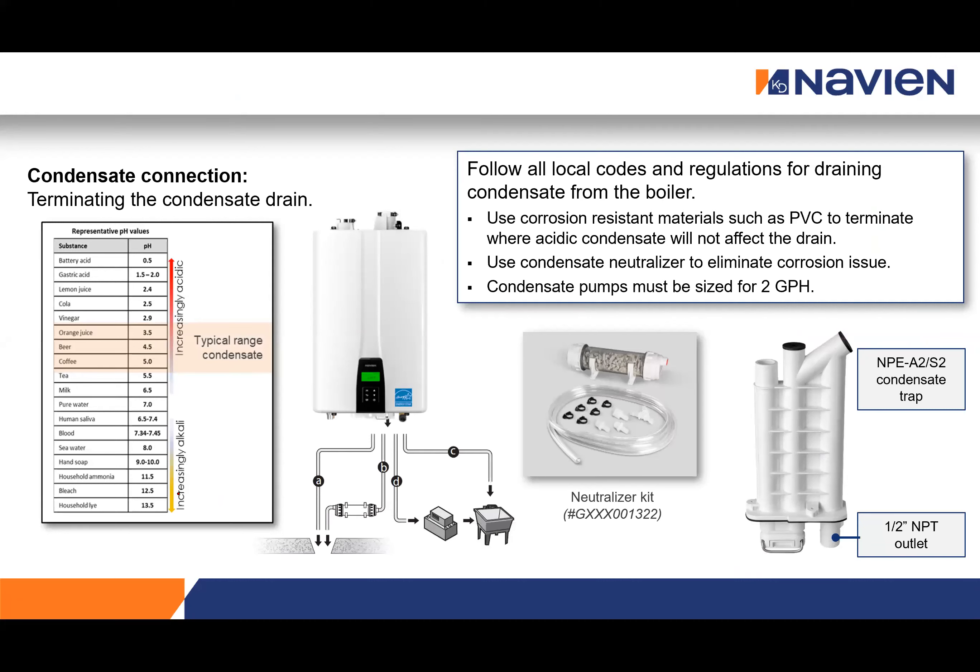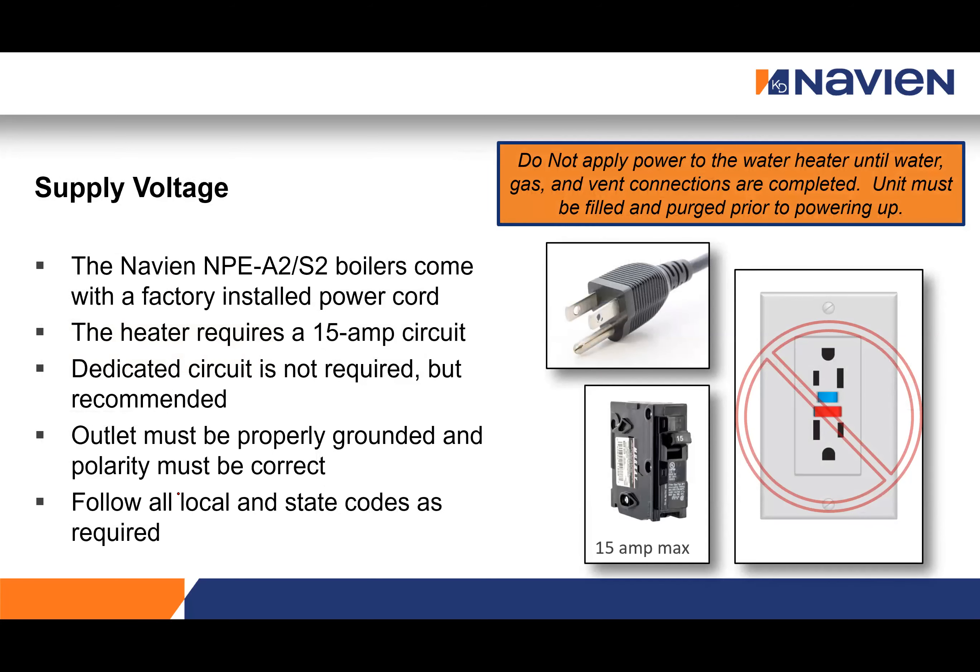Note that condensation from condensing tankless units is acidic — about pH 4 — so it will eat away at metal materials. Make sure condensate drains go to a drain that can handle acidic condensation, or use a condensate pump and/or neutralizer. The condensate connection is a half-inch NPT on the bottom. All Navien products come with a power cord with a three-prong plug. A dedicated circuit is not required but is helpful to ensure proper power. If inspectors require GFCIs or AFCIs, we don't suggest using them as they can cause nuisance tripping — instead, hardwire the unit.